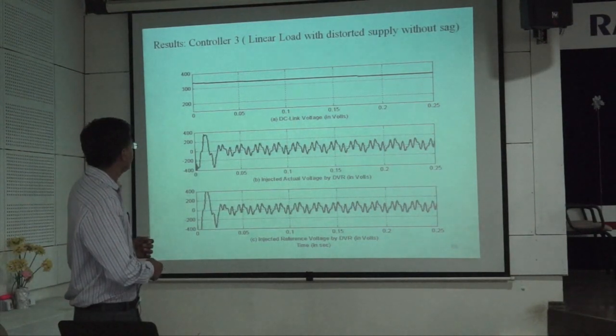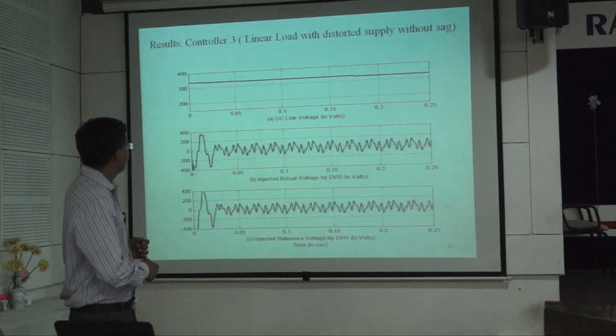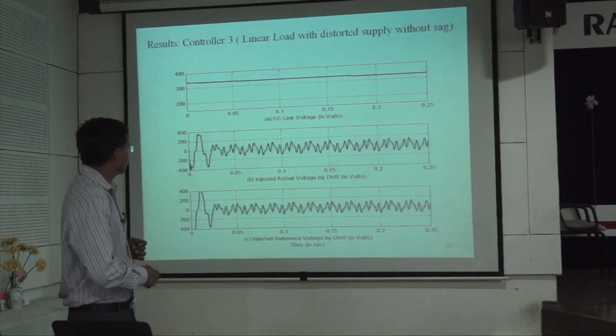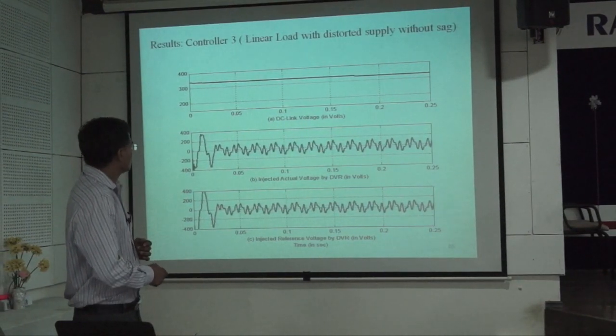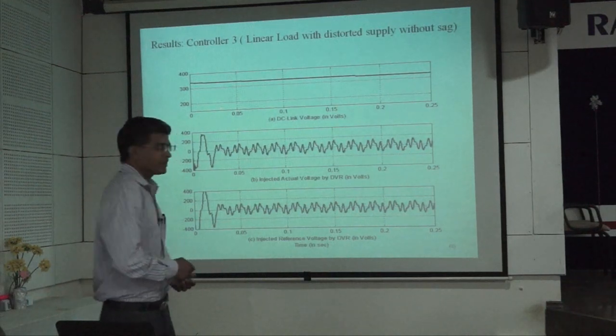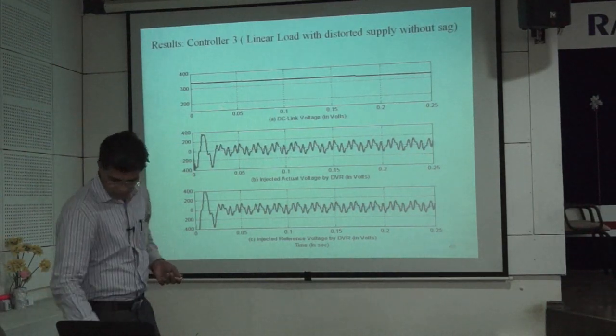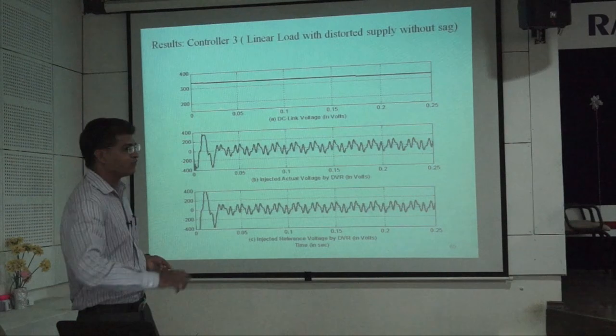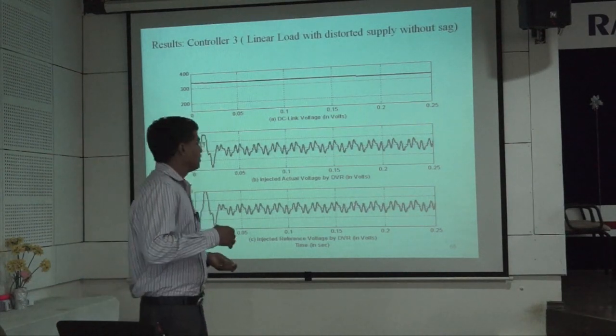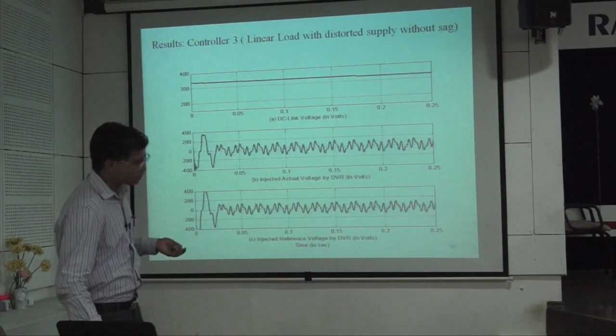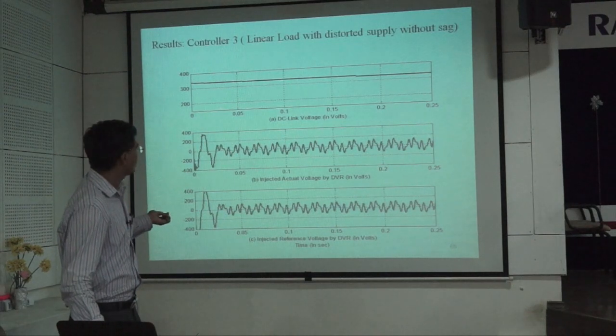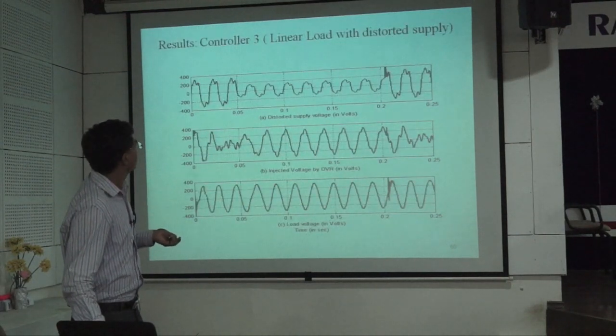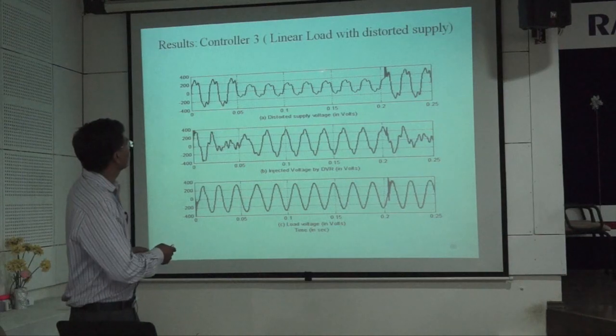This is the actual injected voltage with certain transients where the DVR is in action. This is the injected reference voltage, both are nearly the same. So from these results, I can comment that this controller is robust enough for the non-linear load as well as the linear load, as well as for the distorted supply condition. Now these are the linear load with distorted supply.